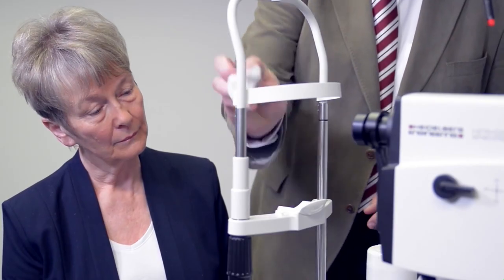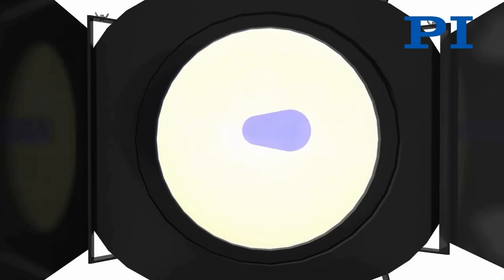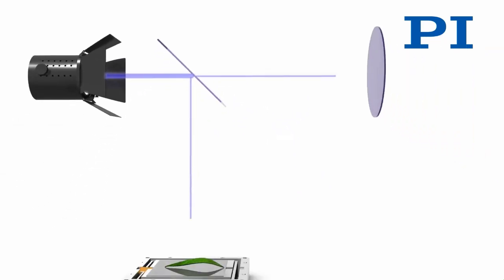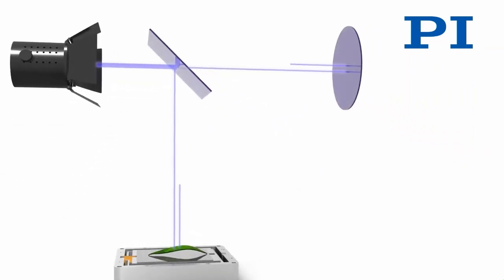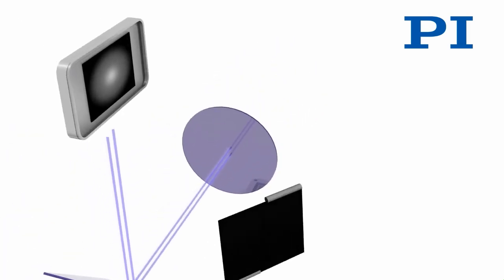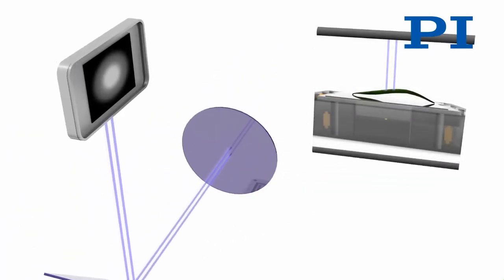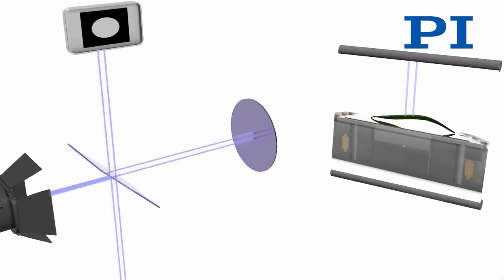The principle of OCT is white light, or low-coherence interferometry. The optical setup typically consists of an interferometer with a low-coherence, broad-bandwidth light source. Light is split into and recombined from reference and sample arms, respectively. Scanning the light beam on the sample enables non-invasive cross-sectional imaging up to three millimeters in depth with micrometer resolution.